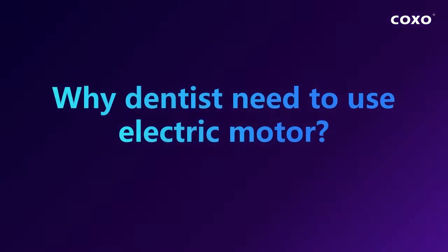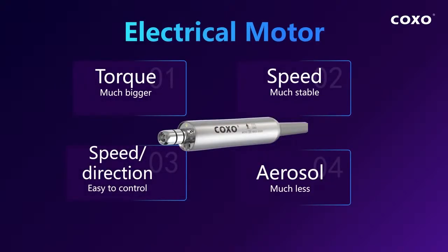Now let's talk about our second superstar of today. First, why does the dentist need to use an electric motor? Compared with the air turbine and the air low-speed handpiece, the electric motor's torque is much bigger. The electric motor's speed is much more stable, and it's much easier to control the speed and the direction. During the treatment, the aerosol is much less than with a high-speed air turbine, because that uses high-pressure air. But an electric motor doesn't need high-pressure air, so the aerosol will be much less.